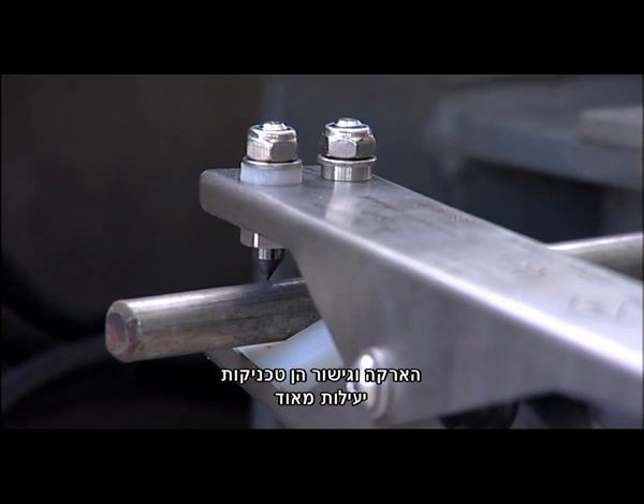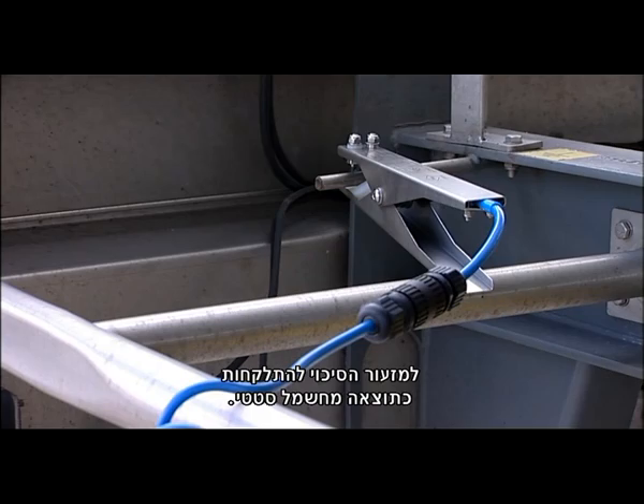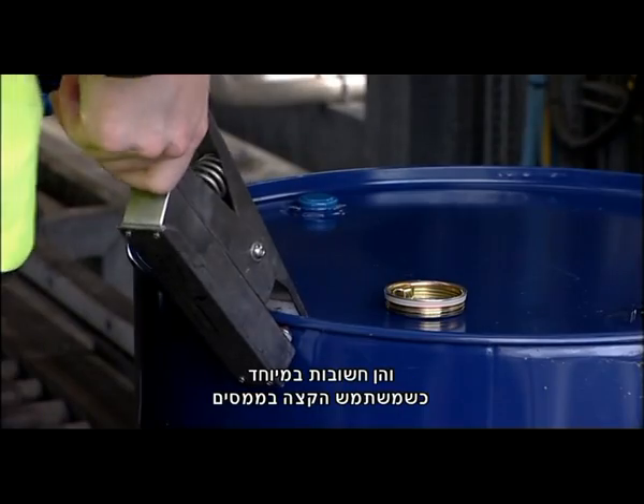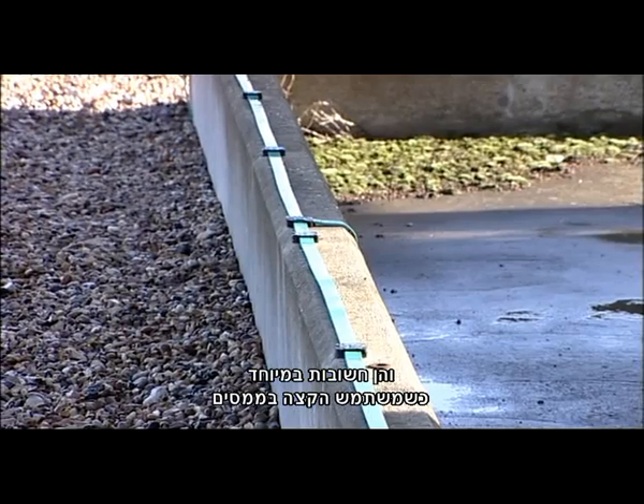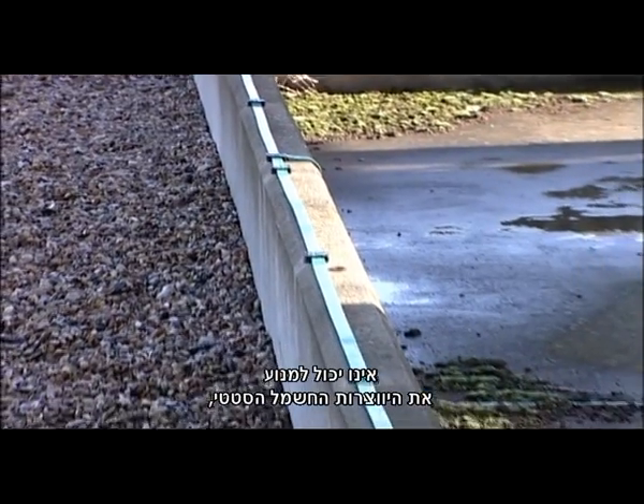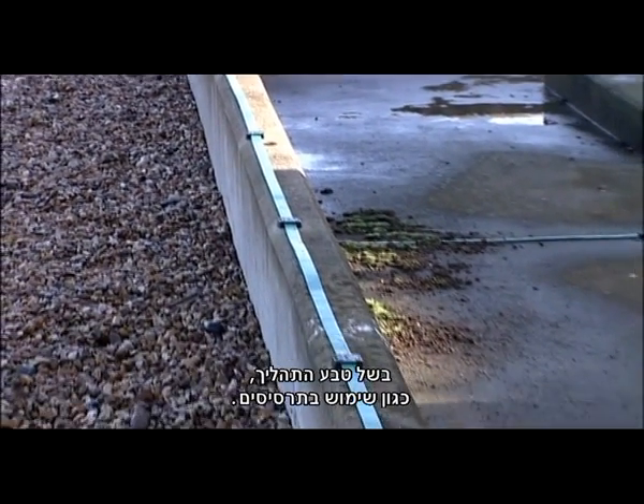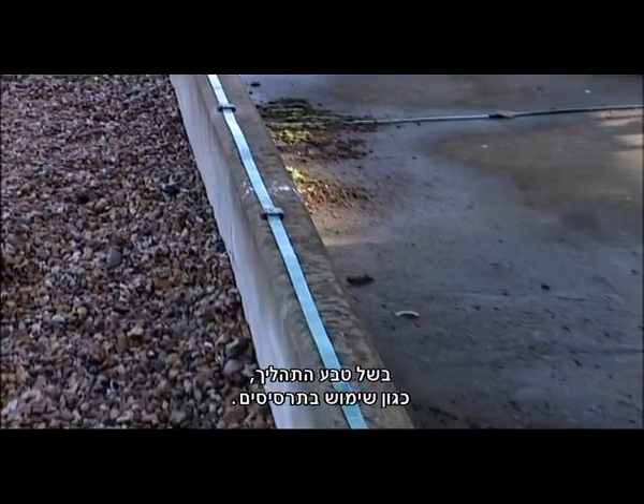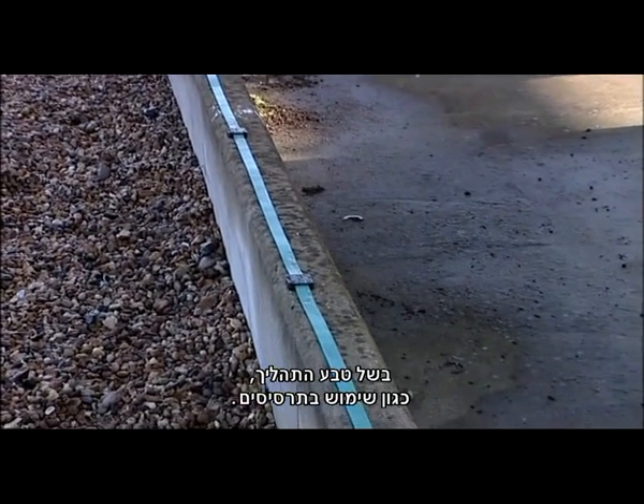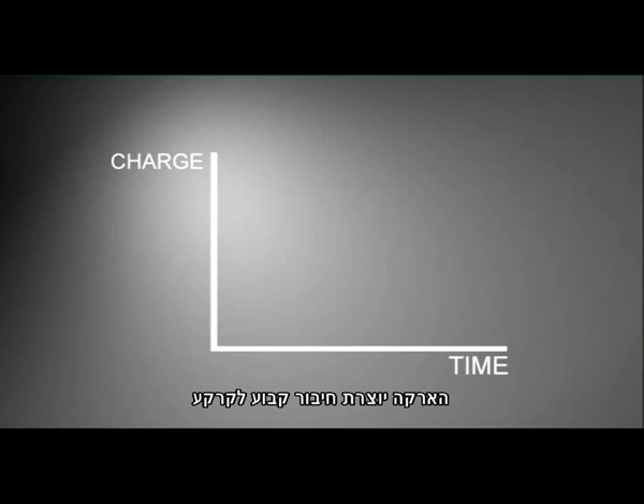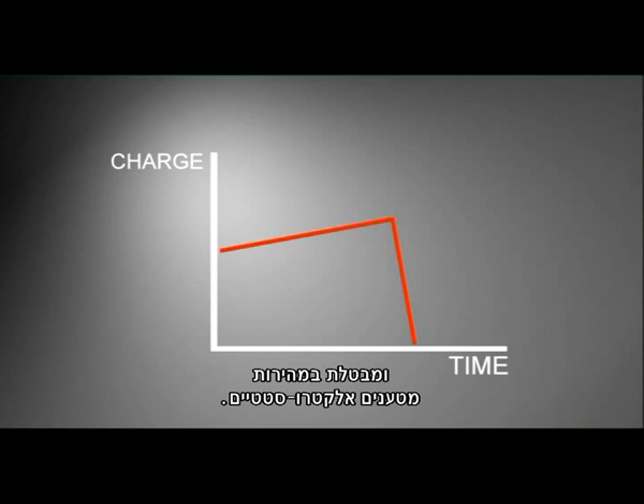Earthing and bonding is a very effective technique for minimizing the likelihood of an ignition from static electricity, and is particularly important where the end user of solvents cannot avoid the generation of static electricity due to the nature of the process, such as a spray application. Earthing establishes a continuous electrical path to earth and will remove charge rapidly.